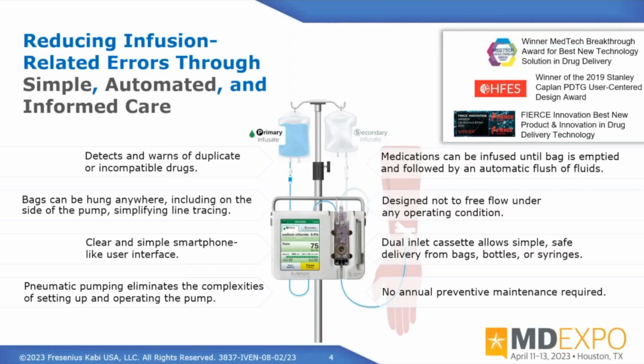And then I talked about the accuracy, and where the accuracy comes in is that the pump actually uses what we call pneumatic technology. So we have a pneumatic system inside the device. It's calibrated, so it calibrates every infusion as it's pumping. And there's two stages to it. So the pneumatic chamber here is kind of like, I say it and I kind of get in trouble with the marketing team, but it's kind of like the shape of a whoopee cushion. Think of that. So we apply pressure to that system and it will pump the fluid into the patient.